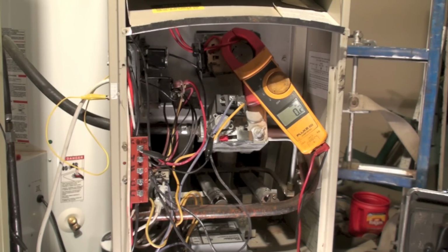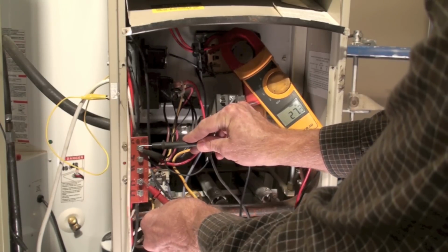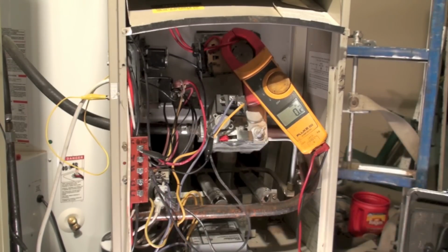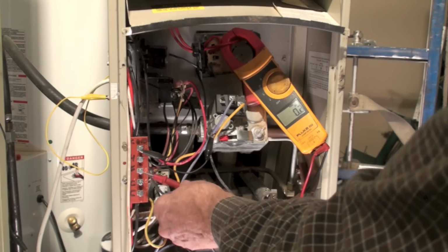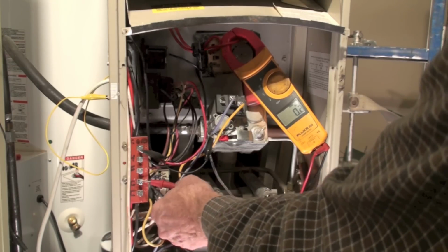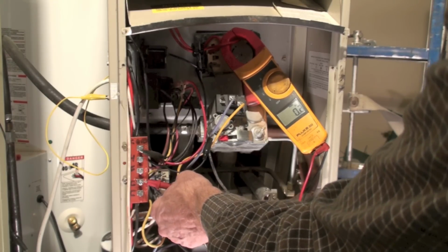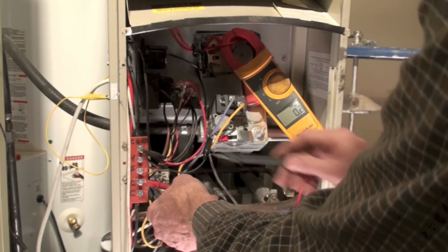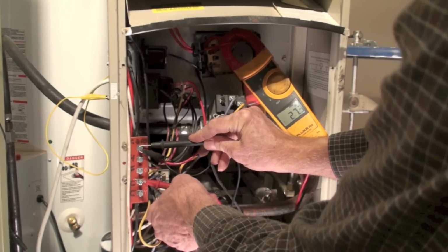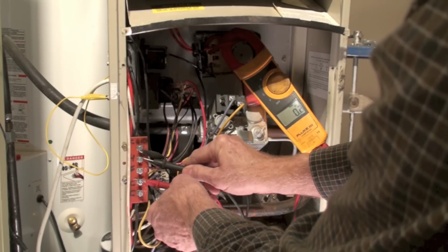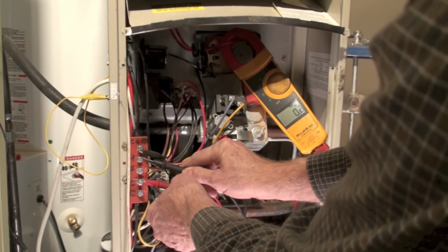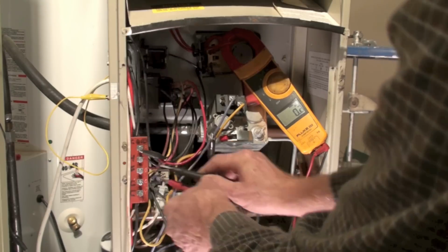Okay, let's say like this one, we had 24 volts right here. Now, do I have voltage through the thermostat? Is the thermostat actually telling the furnace to start? Again, I can keep my probe on C. This is between C and R. Now, if I go to R, I get 26. Now, if I go to W, which is heat, and I show nothing at all, then I have a thermostat problem.